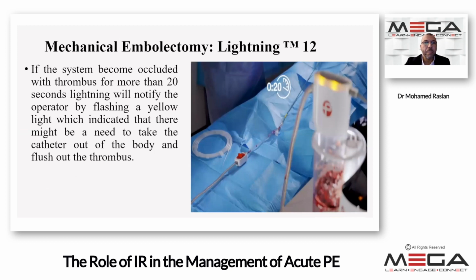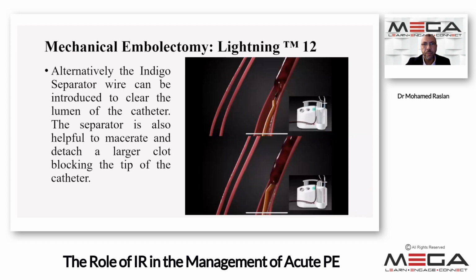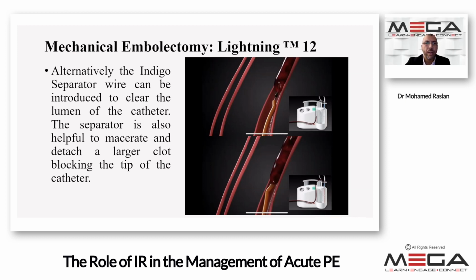If the system becomes occluded with thrombus for more than 20 seconds, Lightning will notify the operator by flashing a yellow light, which indicates that there might be a need to take the catheter out of the body and flush the thrombus out. Alternatively, the Indigo separator wire can be introduced to clear the lumen of the catheter. The separator is also helpful to macerate and detach large clots blocking the tip of the catheter.